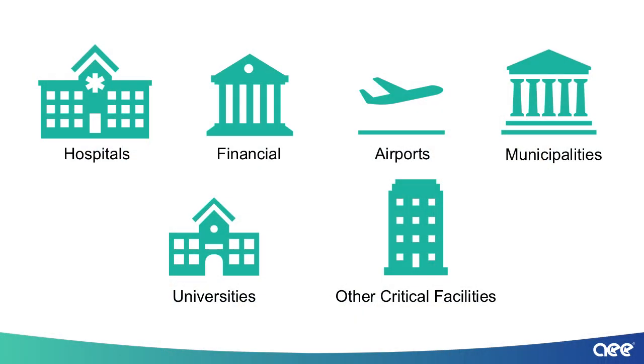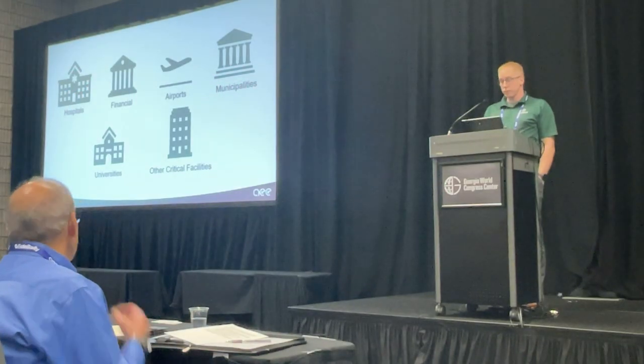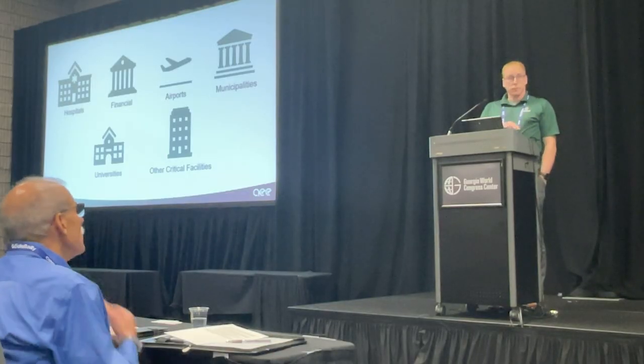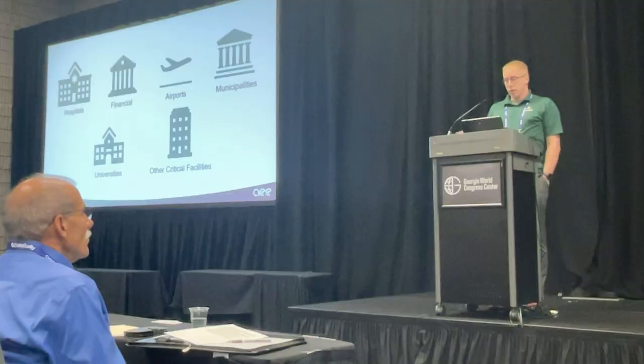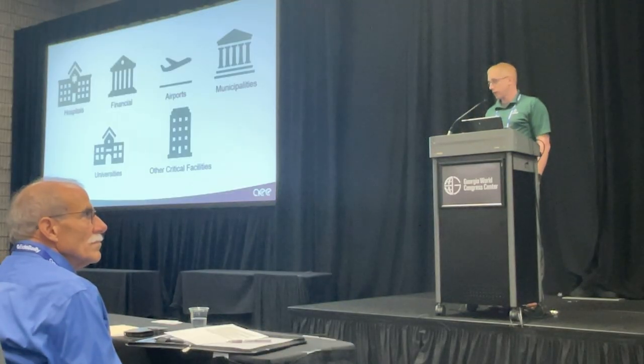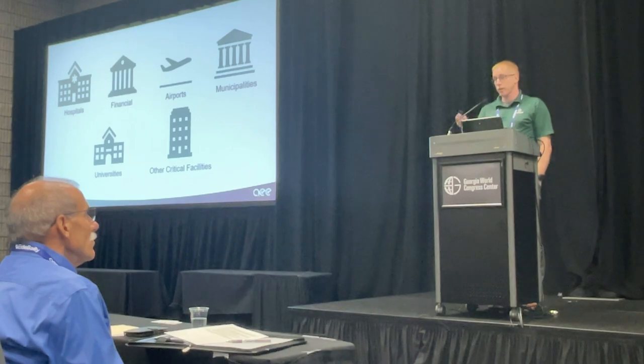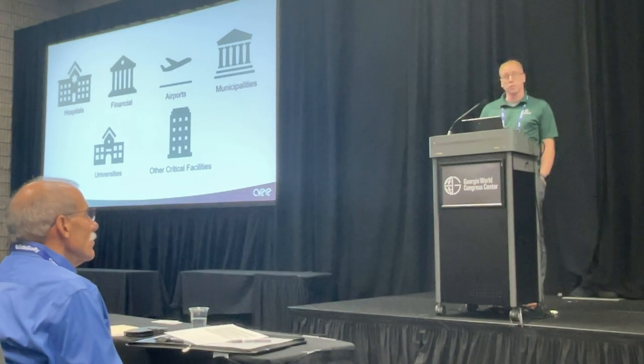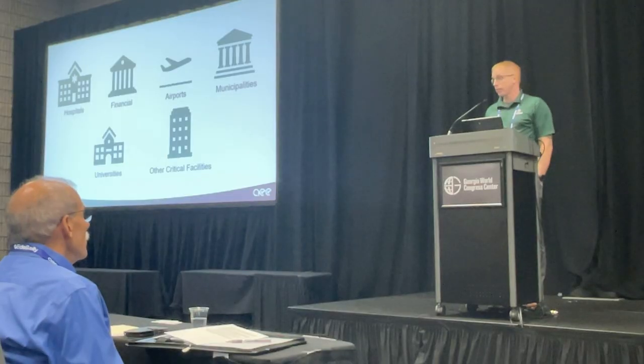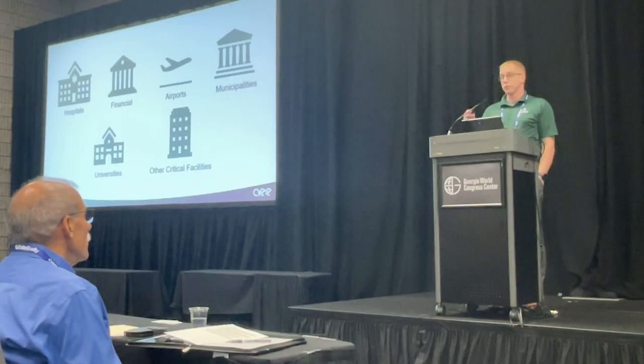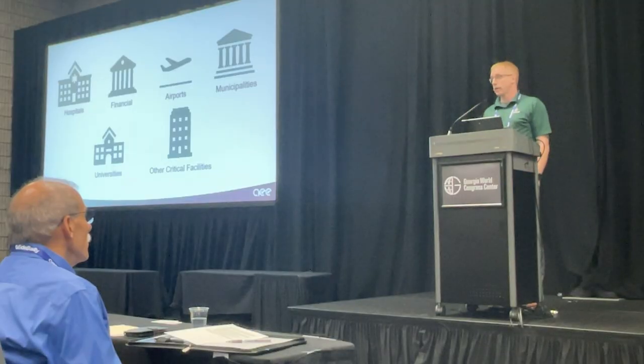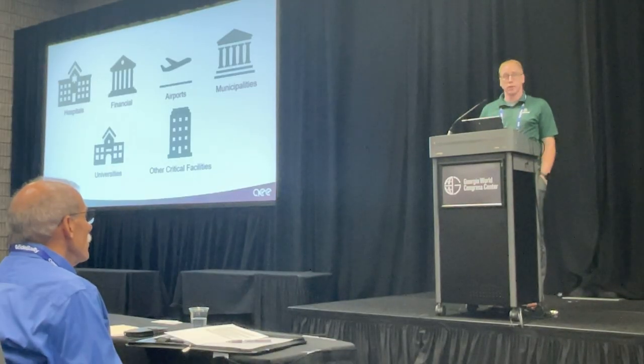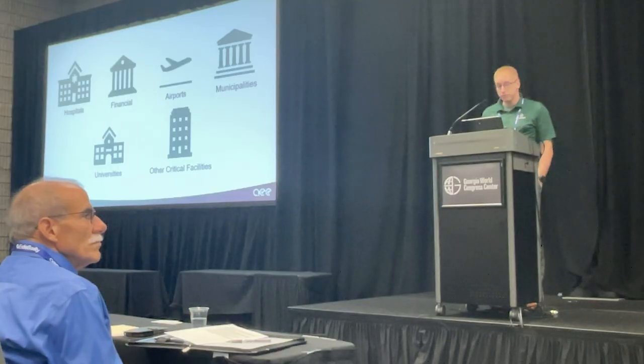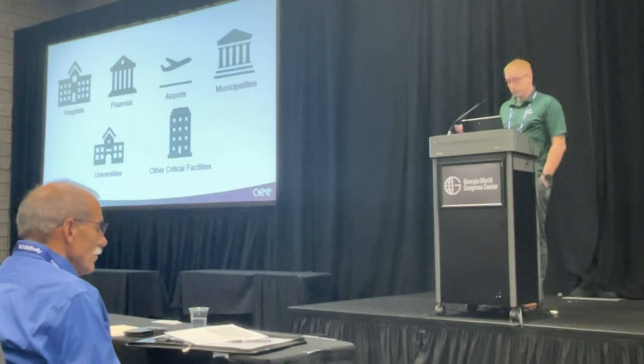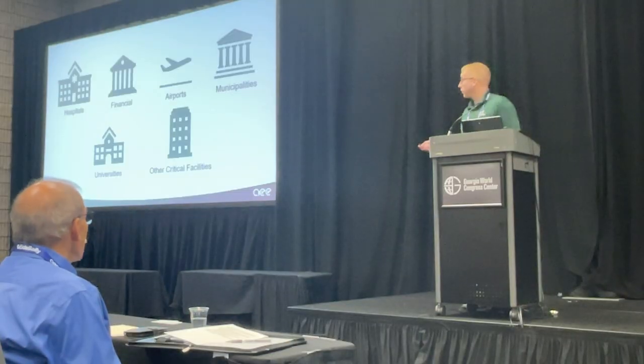NFPA also specifies how long emergency power must be supplied, and for critical infrastructure, it specifies the duration of fuel storage that must be on site. Hospitals require at least 96 hours of fuel storage so they can operate during an emergency. Our local hospital has 7 days of fuel on site, and there isn't currently an alternative backup power system that can provide that with the reliability required for 7 days. There will be, but for now, this is what we have.